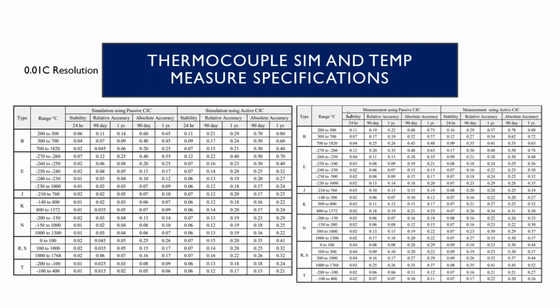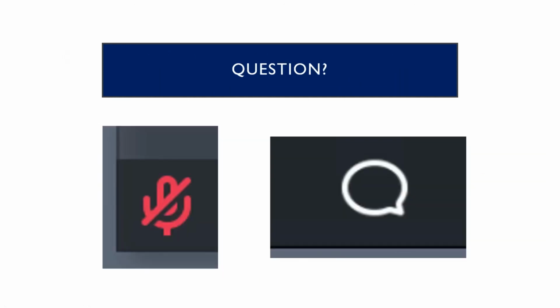And here's the thermocouple. So we were looking at 0.8 C when we looked at the Fluke for the accuracy. And we'll see, simulating with a K thermocouple, instead of 0.8 C, we're at 0.01 C. Okay, that's 24 hours, that's not fair, let's put it out to 1 year: we're 0.03 C. And then for measuring on the back, our 1 year accuracy is 0.07 C. So that gives you some detailed specifications as to our performance.